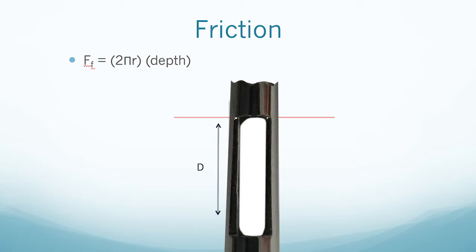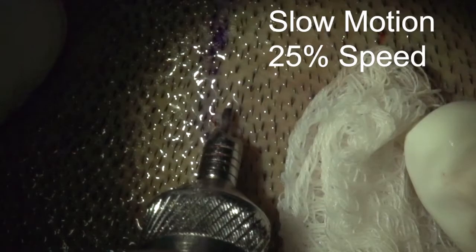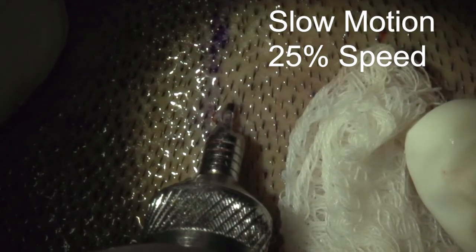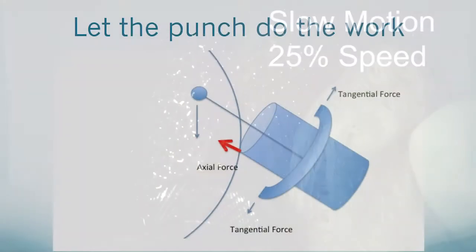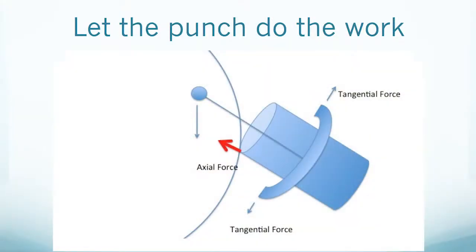In short, resistance is a function of the depth of the incision and the diameter of the punch. So resistance is equal to the depth times 2πr, where r is the radius. Opening the sides of the punch reduces resistance as the punch enters the skin. A reduction in resistance internally allows for easier penetration of the punch with less axial force. A high axial force always increases the probability of follicle transection.